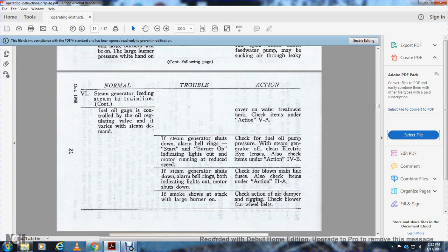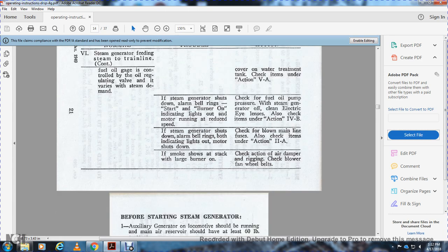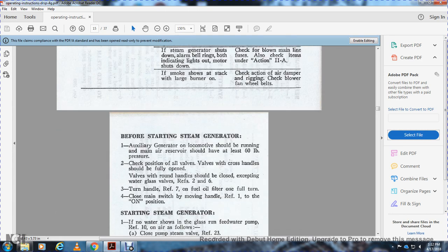If the smoke shows at stack with a large burner on, check the action of the air damper and the rigging, and check the blower fan wheel belt. Before starting the steam generator, the auxiliary generator on the locomotive should be running and the main air reservoir should have at least 60 pounds pressure.